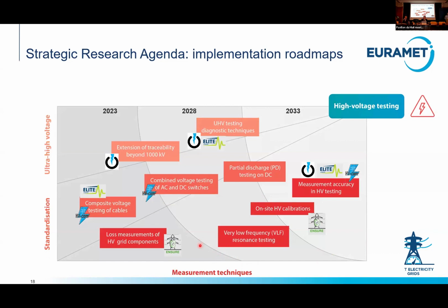We've seen the presentation before from NMIA. You need big labs, big facilities, but as the grid expands, as we see higher and higher voltage levels on the grid, we need to be able to keep up with the pace of the grid development. So ultra high voltage is a big field of development. Ultra high voltage testing, going above a megavolt, extending the traceability of the NMIs in that area, but also defining standardization for what kind of waveforms you test, what devices need to be tested, so cables, AC and DC switches, partial discharge, and that goes alongside measurement techniques.